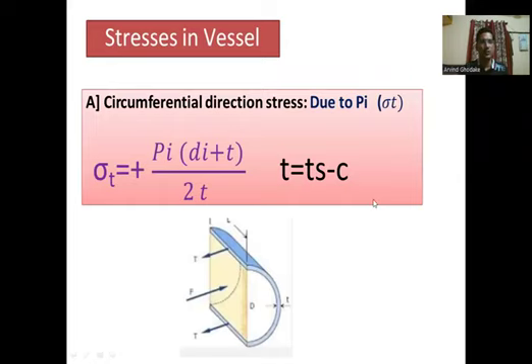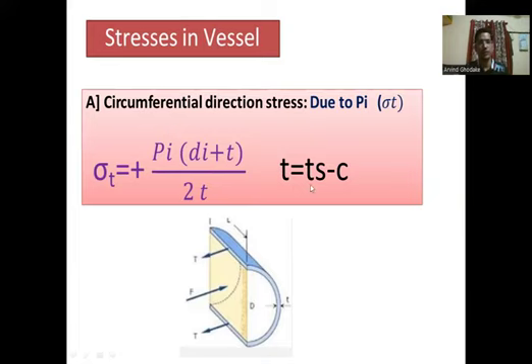Next are the stresses in the vessel. The first stress in an unfired pressure vessel is the circumferential stress, which occurs due to internal pressure PI. The circumferential stress sigma_T = PI × (DI + T) / (2T), where DI is the inner diameter and T is the effective thickness (shell thickness minus corrosion allowance).